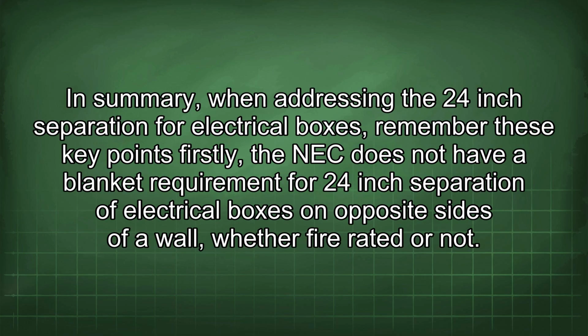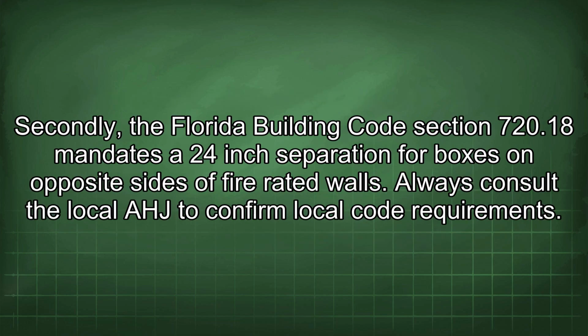In summary, when addressing the 24-inch separation for electrical boxes, remember these key points. Firstly, the NEC does not have a blanket requirement for 24-inch separation of electrical boxes on opposite sides of a wall, whether fire-rated or not. Secondly, the Florida Building Code Section 720.18 mandates a 24-inch separation for boxes on opposite sides of fire-rated walls. Always consult the local AHJ to confirm local code requirements.